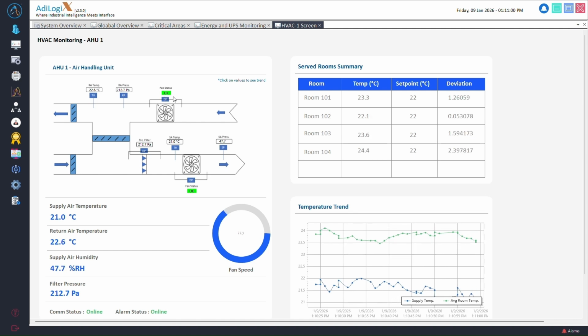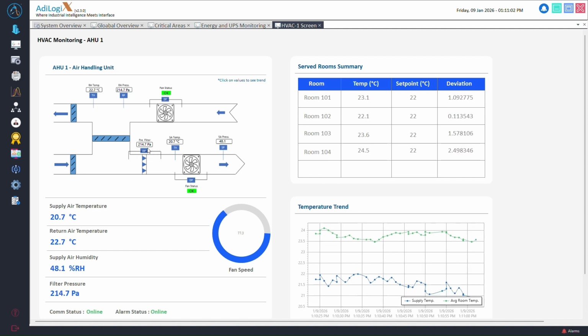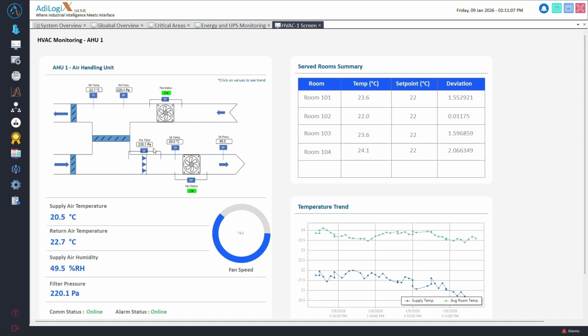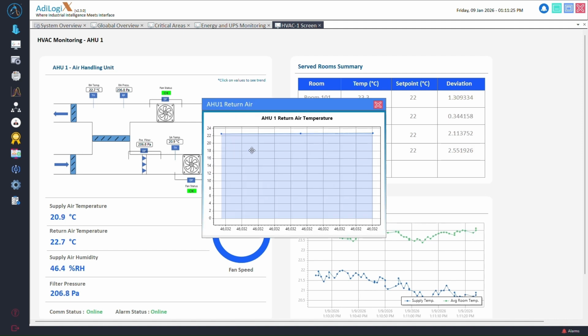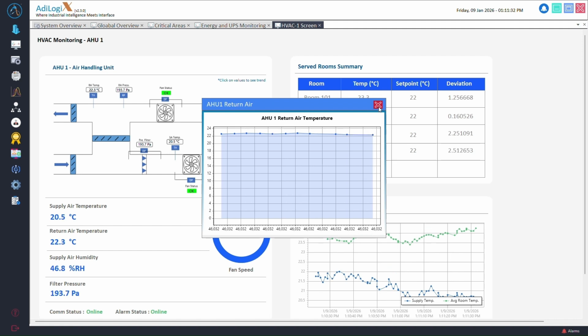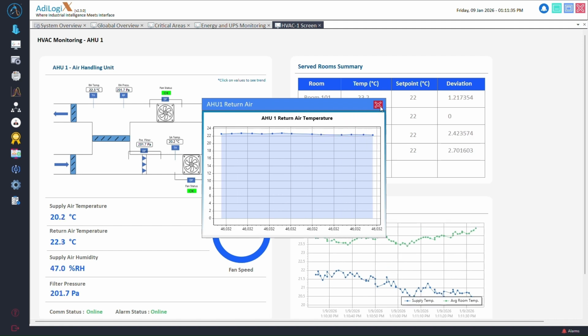Filter pressure drop continuously tracks filter health. Supply air temperature and pressure verify cooling performance. Every value displayed here is directly sourced from BACnet IP field devices, no calculated assumptions. Each numeric label on the AHU diagram is interactive. By clicking on any live value, temperature, pressure, humidity, or fan parameters, the system instantly opens a real-time trend view for that specific point. This allows engineers to move seamlessly from overview to analysis without leaving the screen.